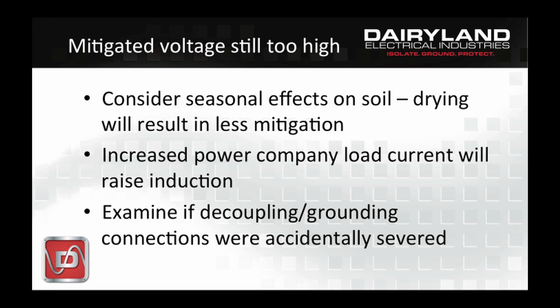There's different effects on the soil in different seasons. Soil can be wet or dry, depending on the time of year, depending on the season. Dry soil has high resistivity, and a mitigation system will be less effective in dry soil, all things equal. Keep in mind also that the load current on the power company's lines will go up and down, and that will affect the induced voltage that you see.